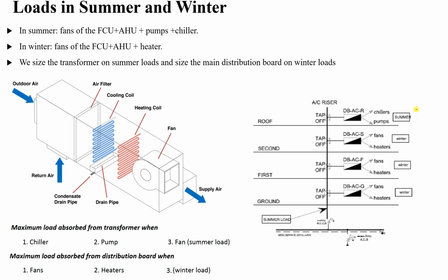Till now everything is great. So we have summer, we have winter. Now my question for you, when you are selecting the electrical transformer, are you going to look for winter loads or summer loads? You are going to design it based on winter or based on summer. Now the answer to this question is pretty simple. I will design based on summer. Now you will ask me, why do you design based on summer?